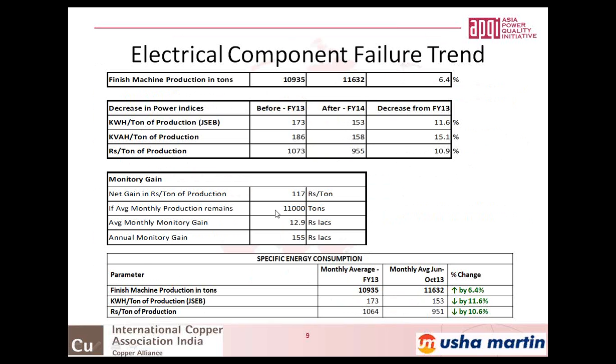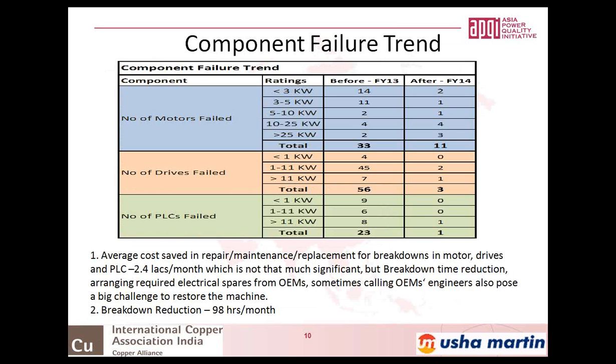Our production is at the level of 11,000 tons per month. So we got a saving of 12 lakh rupees per month, an annual saving of 1.5 crore. These are the major monetary benefits we got. But if we see the component failure trend, before installation of these filters we were having motor failures at the level of 33 motors per month, which reduced to 11.